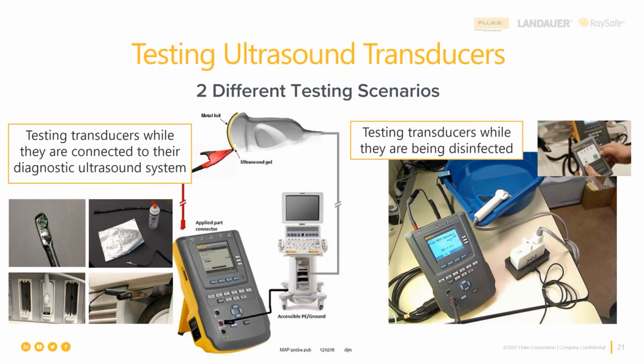When it's run on the ULT, or the electrical safety analyzer, the leakage current values are going to be much, much lower than they would be if we had that transducer connected to its diagnostic ultrasound system and we ran the mains on applied part test through the whole system. That leakage current value will be a bit higher than it would be in the cleaning solution basin.